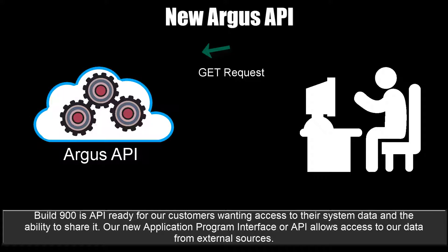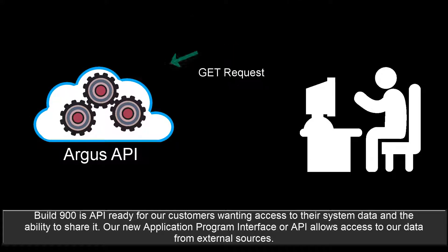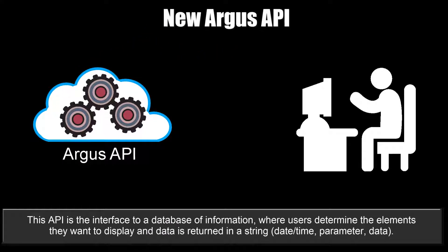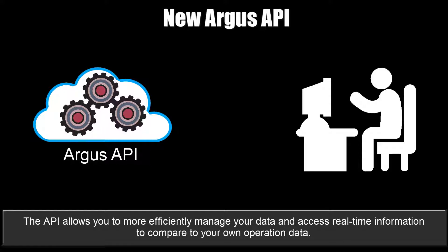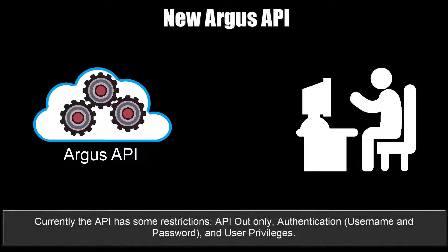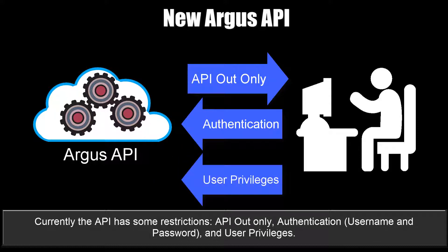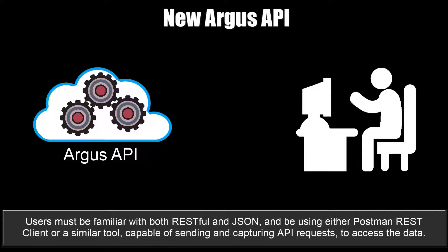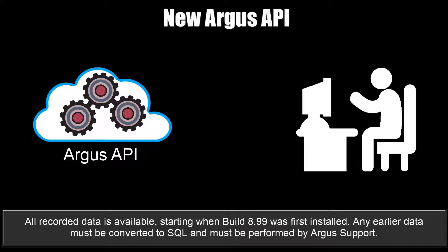Build 900 is API ready for customers wanting access to their system data and the ability to share it. The new application program interface, or API, allows access to data from external sources. This API is the interface to a database of information, where users determine the elements they want to display and data is returned in a string — date, time, parameter, data, and so on. The API allows you to more efficiently manage your data and access real-time information. Currently, the API has some restrictions: it is output only, requires authentication with a username and password, and users must have appropriate privileges. Users must be familiar with RESTful and JSON and be using Postman, REST Client, or a similar tool. All recorded data is available starting when Build 8.99 was first installed; any earlier data must be converted to SQL by Argus support.